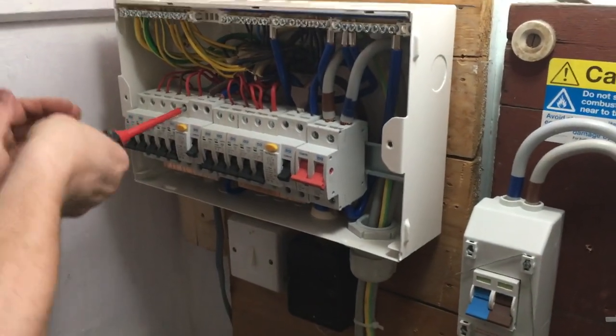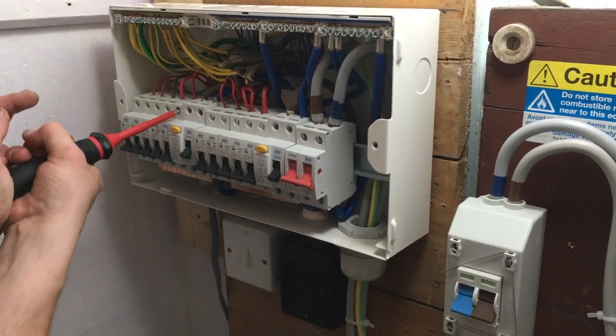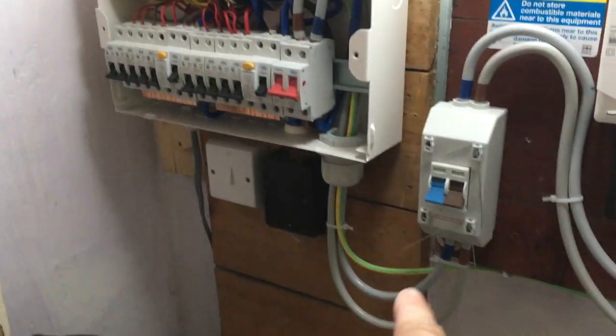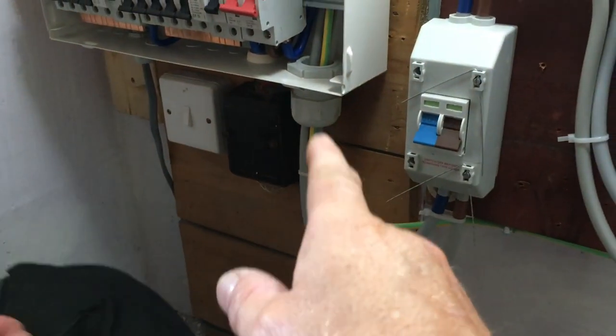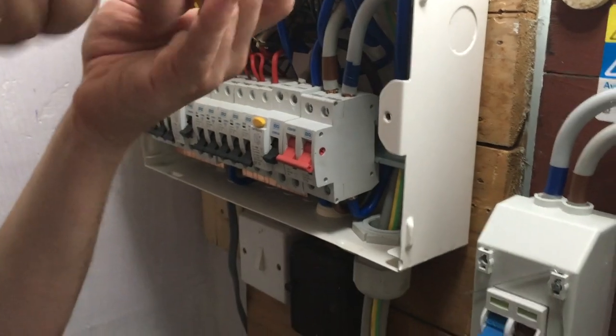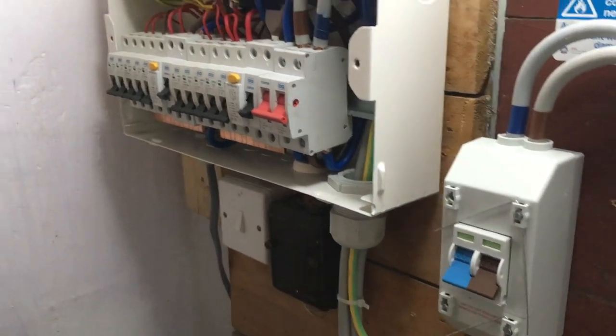We're torquing up the terminals with our torque screwdriver. We've got the main isolator in, our 25mm tails, and the earth going into the Wiska box — just tightening all the terminations. That's where we are with it so far; we've still got a lot of testing to do and stuff like that, but it's coming on.